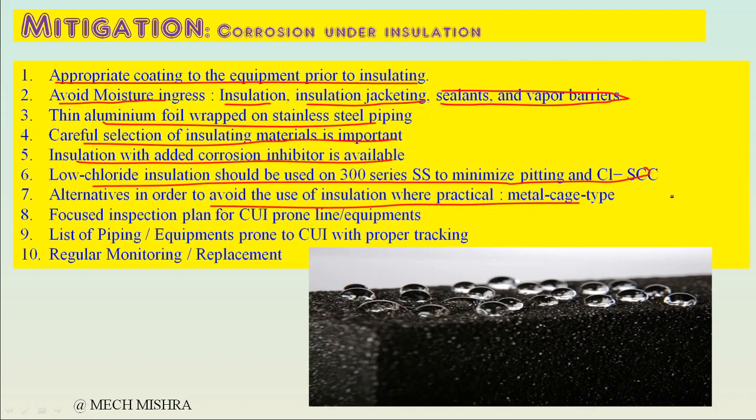that will also protect. Okay, so then a focused inspection plan for CUI prone equipment and lines. We have to prepare a list of equipment and piping which are prone to CUI based on the guideline, and we have to keep a better monitoring system for that focused inspection plan for those equipment and piping, and we have to track them also. So a list of piping and equipment prone to CUI with proper tracking.